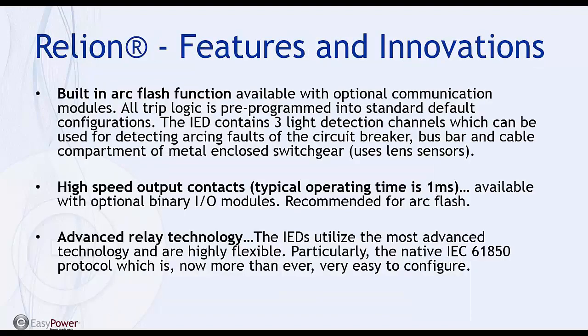Okay, now we're going to switch to our other product that has the arc flash function built in, which is Relion. Here you have the optional communication module that has the arc flash sensors, which are lens sensors. That doesn't quite offer the same coverage that the loop sensors do, so that could be considered one slight drawback. The other is that the speed is not quite as fast, but like we discussed before, it's not much slower, and for all practical purposes, you're offering the same protection that you would with the REA. So that's basically the idea there.